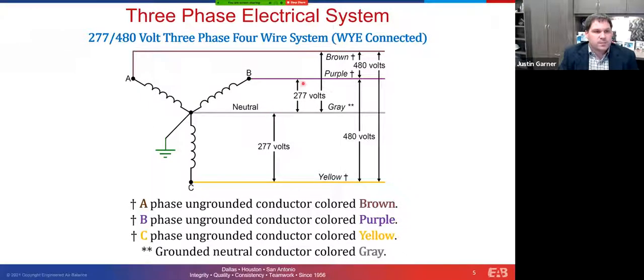And so what's interesting to note here, again, is we have three ungrounded conductors. So we have a phase A here, phase B, and a phase C. I have these color-coded the way that you can see them in the field, but you may see other colors. It's important to note that you should have three distinct colors there. And then typically in this system, a neutral would be gray as opposed to white. But the code only stipulates that they'd be distinct colors and used uniformly throughout a facility.